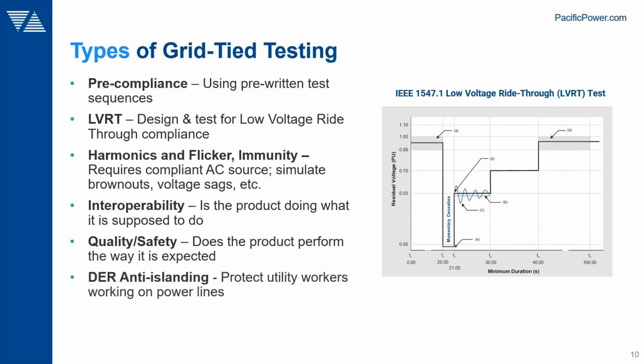Finally, for some energy storage and energy generation devices, anti-islanding is a particular aspect that has to do with worker safety of utility workers. If part of the grid gets de-energized for whatever reason, any distributed energy resource connected to it has to detect that in a timely fashion and stop generating power to the grid so line workers can go in and fix the problem. Without that, their safety would be at risk, which is not acceptable. So anti-islanding is a very important test for PV and solar inverter products.